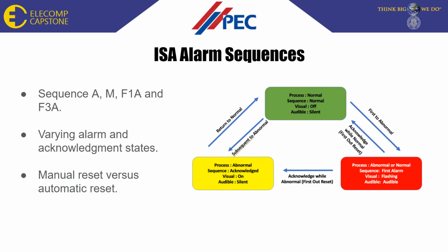The first task I accomplished was to design an alarm system that fulfilled the requirements of the International Society of Automation, also known as the ISA. Four alarm sequences were designed, each a little different from the other. Sequence A was the simplest, with an automatic reset. Sequence M was near identical, the only difference being a manual reset required at the end. The last two sequences, F1A and F3A, were both automatic resets with first outs and more alarm and acknowledge states.